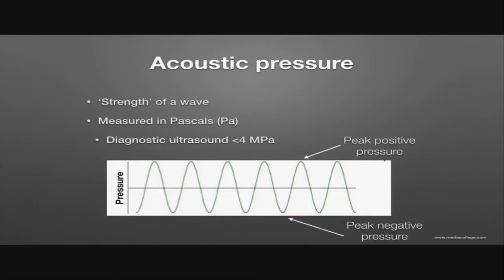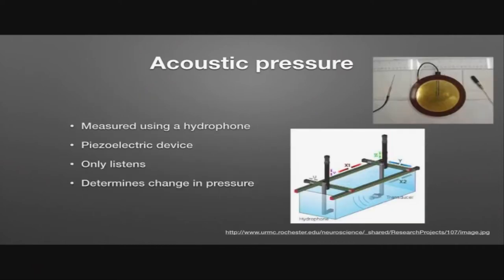Acoustic pressure is the strength of the wave. We typically measure that in pascals. In diagnostic ultrasound, it's less than 4 megapascals. You get a peak positive pressure through compression of the sound wave molecules, as opposed to during rarefaction when those particles are separating, giving you the negative pressure. This is important when considering the mechanical effects on tissue. We can measure acoustic pressure using a hydrophone — a piezoelectric crystal device that only listens and doesn't transmit ultrasound — placed in a bath with the transducer to determine the change in pressure.